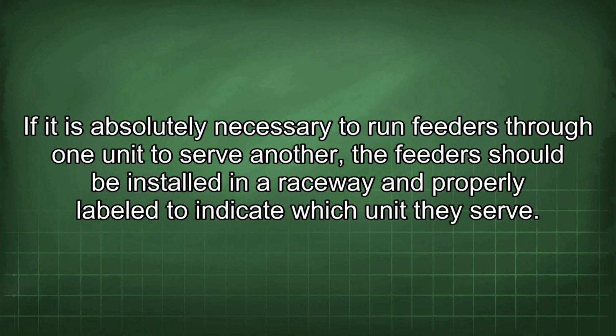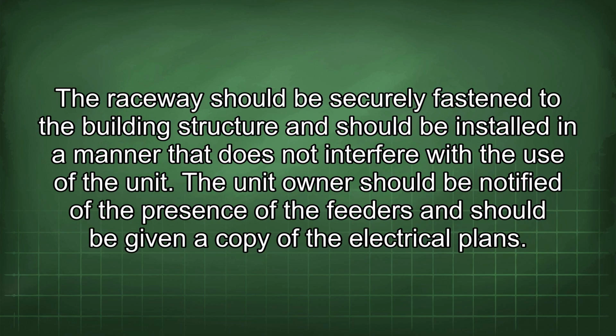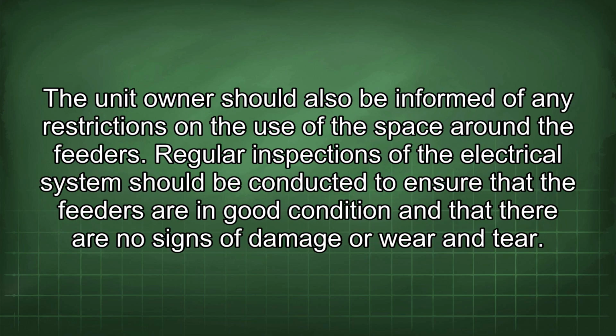If it is absolutely necessary to run feeders through one unit to serve another, the feeders should be installed in a raceway and properly labeled to indicate which unit they serve. The raceway should be securely fastened to the building structure and should be installed in a manner that does not interfere with the use of the unit. The unit owner should be notified of the presence of the feeders and should be given a copy of the electrical plans.